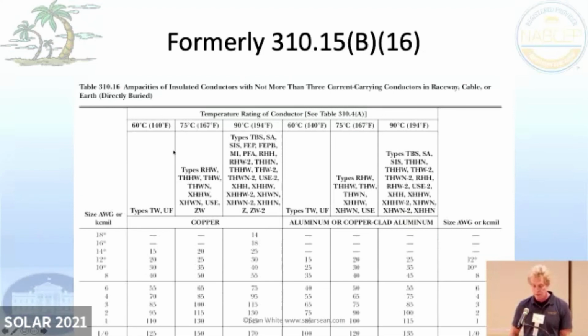And this is probably the most widely used page in the NEC book. If I had a number 10 wire and the insulation around that wire is rated 90°C, so that insulation could heat up to 90, then I could put 40 amps through it before it heated up too much and would, in theory, wreck that insulation. Usually it can carry a lot more current than these tables say. There's a lot of safety factors written in there. So this is a very common page to figure out how big a wire should be.